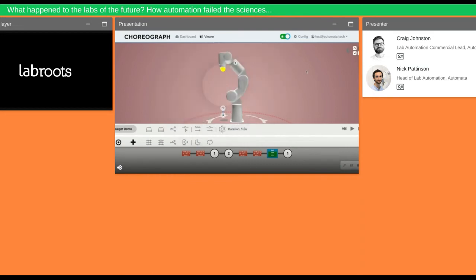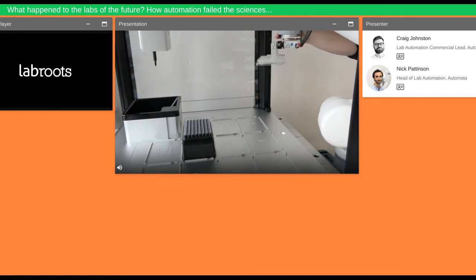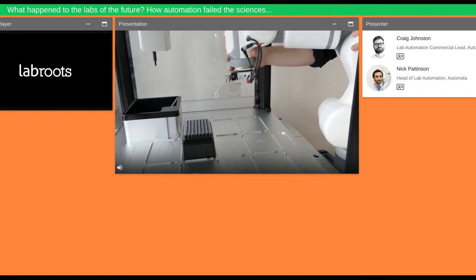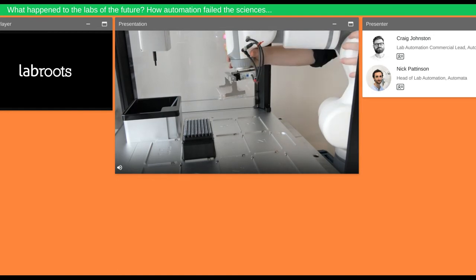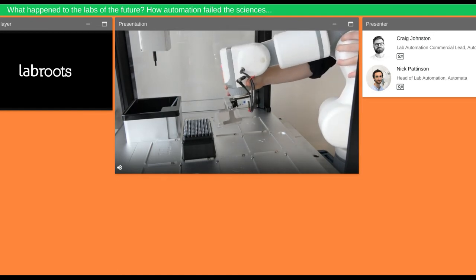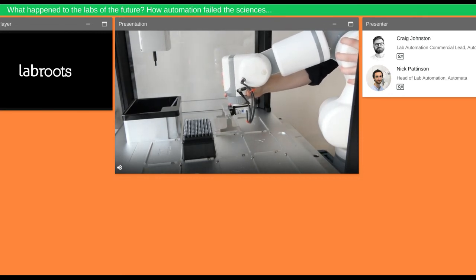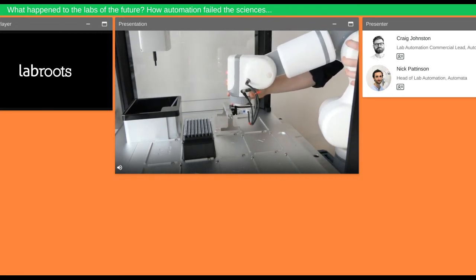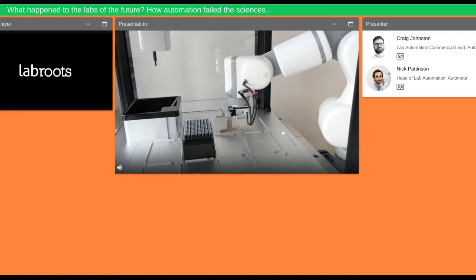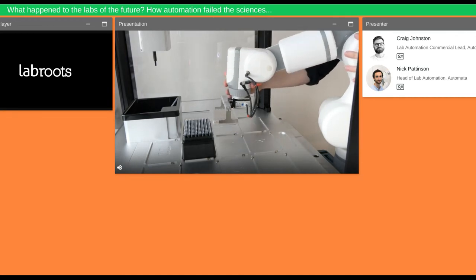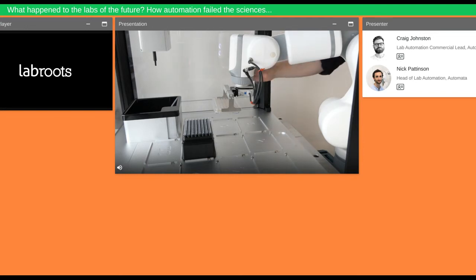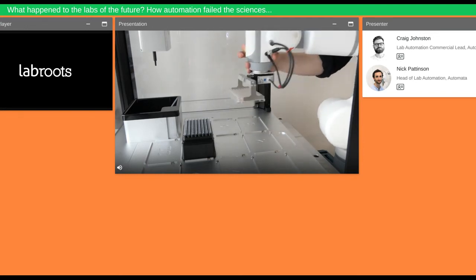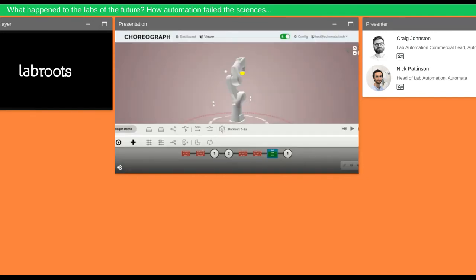And as you can see there in Choreograph, the robot now moves it up for it ready to move in. So when we're putting the microplate in, we're almost going to do the exact opposite of what we did earlier. So earlier we hovered over the microplate, and then we moved down to pick it up. Whereas this time, all we're going to do is we're going to move the microplate right into position. So press right against the base, like that. And then we're going to save that waypoint. And then in Choreograph, all we're going to do is duplicate that waypoint and move it up by that 40mm we moved it up by earlier. So it's around this position. And that means we can get that straight vertical pickup, and we won't catch any of the lab ware in there. So what we're going to do now is jump into Choreograph and do that little duplication. So that's my first bit of editing trickery. I've just duplicated that point like I did earlier. But we started, I guess, eight minutes ago now, and we've got all the building blocks that we need to program our full toolpath.